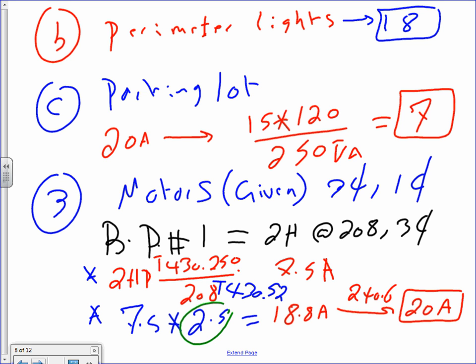Higher than 18, what do you do? Another branch circuit. So if you came up with 21 lights, it's a good idea to split them, even from a maintenance point of view, guys. 21 fixtures around the building, split them into 2 circuits. 21 fixtures in one area, split them into 2 circuits. Does that make sense? So you do perimeter lighting the same as you do indoor lighting? Yes, based on the same criteria, the 100 volt amp assumption.